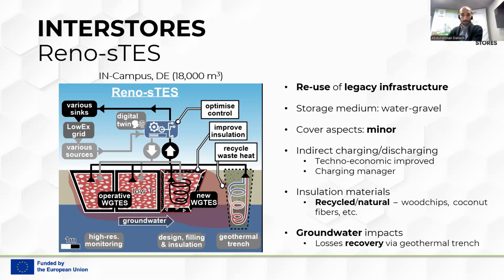Those three basins are going to be filled with water gravel as a storage medium. The main idea behind using water gravel is that it increases the structural and mechanical stability of the basin, or the entire seasonal thermal energy storage, leading to a significant reduction in cover costs. If you look at the Danish experience, you'll find that the major part of the capex goes most of the time to the cover, and we would like to get rid of that. That's why we decided on water gravel as the filling material for the three basins, in order to reduce the cover aspects and cover-specific costs.